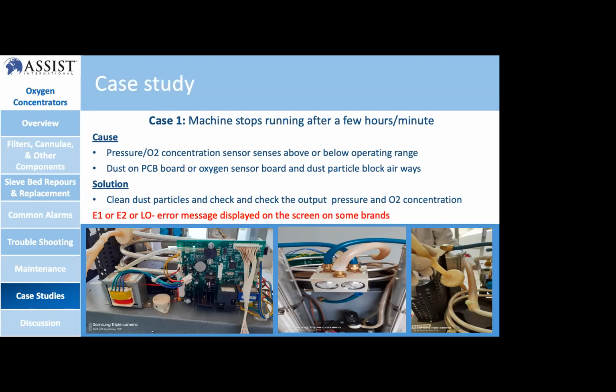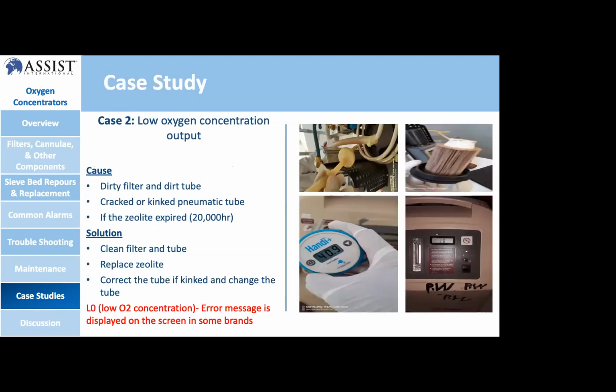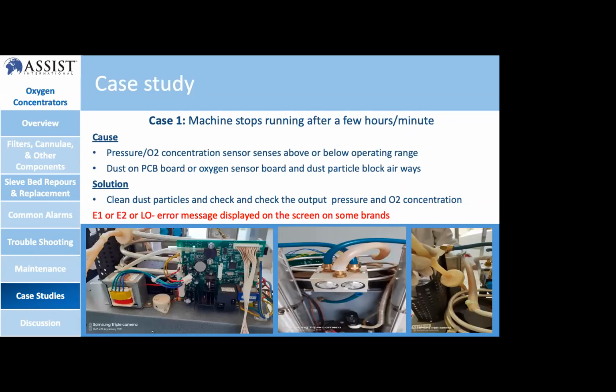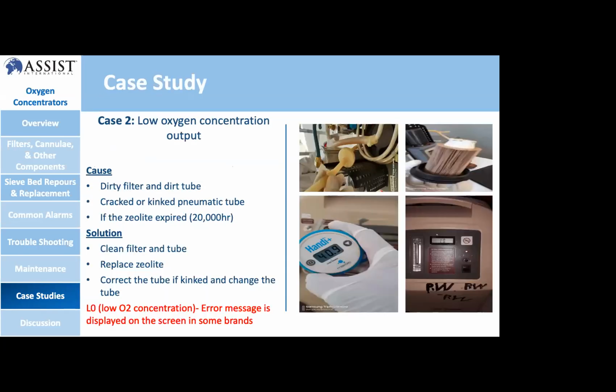As you see in the image, we have dust on circuit boards, and we have a leakage on a solenoid valve here. That means if there is a leakage, it causes low pressure delivery to the patient, so the machine has to keep working. Next slide.